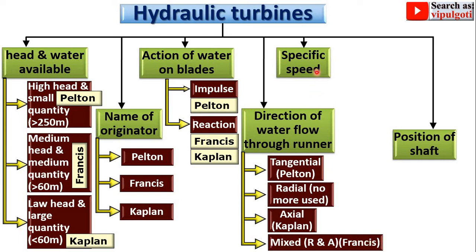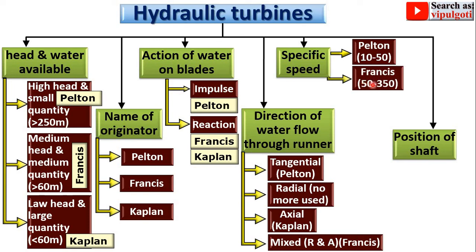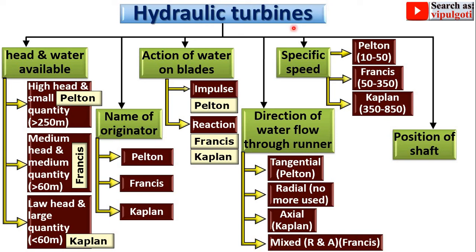Next, classification according to specific speed. Low specific speed of 10 to 50 — the Pelton turbine is suitable. Medium specific speed of 50 to 350 — the Francis turbine is suitable. High specific speed of 350 to 850 — the Kaplan turbine is suitable. So generally these correspond to low, medium, and high specific speed hydraulic turbines.